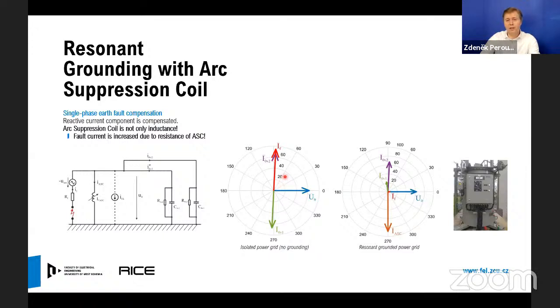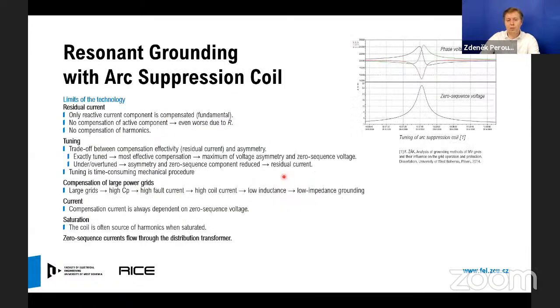So this is the state-of-the-art technology, having several limits. What are the limits which I see with the arc suppression coil operation? Definitely one of the big problems is residual current, because the arc suppression coil is able to compensate only the reactive current component of the fault current, and only the fundamental component of this fault capacitive current. The arc suppression coil is unable to compensate the active fault current component, and it is unable to compensate the higher harmonics in the fault current. The problem is also complex tuning, which is not an easy task.